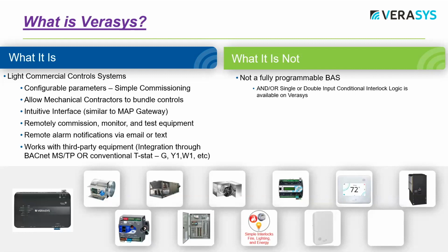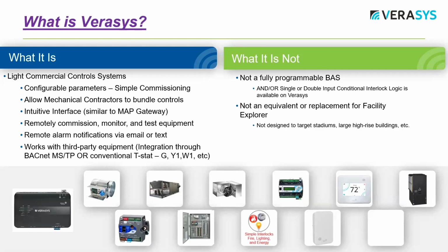We ship our higher level controls pre-programmed with applications specific to the needs of that customer or project. If you want to do a VAV system, we have controls specific for VAV. If you're doing changeover bypass, we have controllers for that. Constant volume, we have that as well. So there's a lot of flexibility, but it's not fully programmable. I feel there are enough parameters within the Verasys system that we should never need to get into the code. You should be able to set this up and configure it through the parameters currently presented in the main Verasys interface.